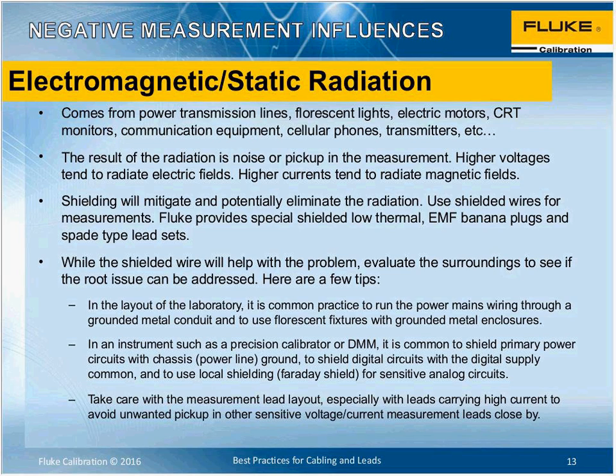So I've noted some of those down there on the side, which is the very obvious one about the layout in the laboratory. Keep any mains wiring in the lab out of the way, run it through some grounded metal conduits, and be careful about the use of those fluorescent fixtures. LED lighting is becoming more common nowadays, and some of that LED lighting is somewhat better. Other lighting also uses high frequency converters, so you have to be, again, careful. Most of the good lighting fittings, of course, have grounded metal enclosures, which help.